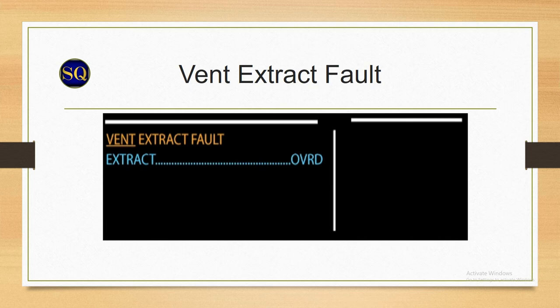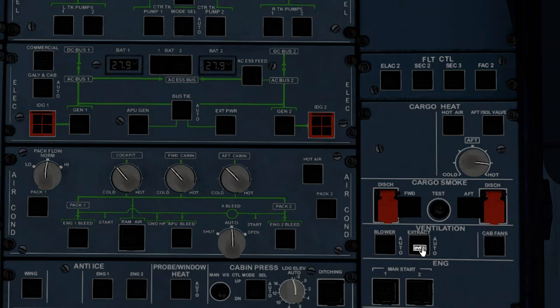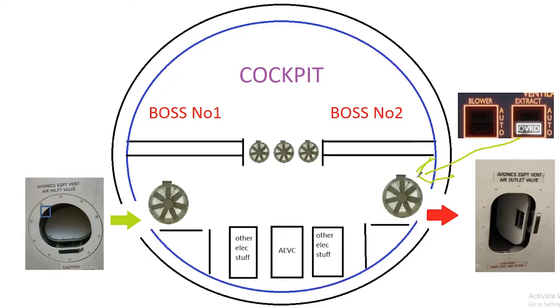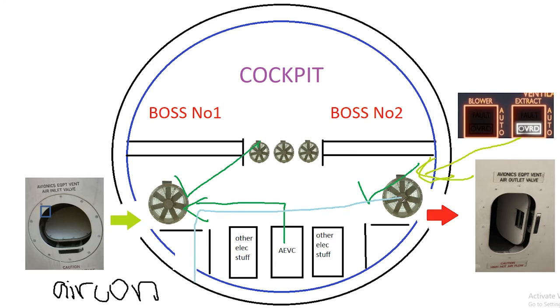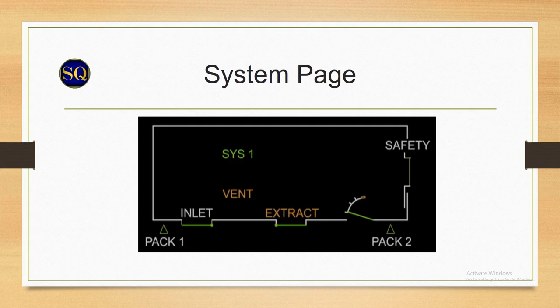Okay, now extractor fault. If the system detects that ventilation pressure is low, the fault light on the extract switch will go on and an ECAM warning is triggered. Fault is also triggered if the AEVC fails. By selecting the extract switch to override, the ventilation fan runs directly from the switch and the blower fan continues to run normally. The system goes into closed circuit configuration with air from the air conditioning system being blown into the system. This will indicate on the system page.